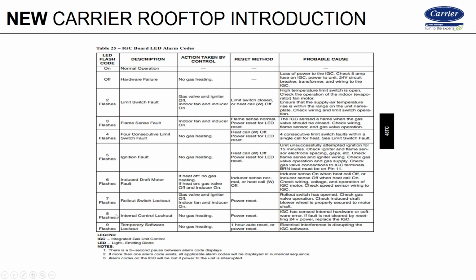So fault code 8, internal control lockout. There's a few things that cause this. Either the IGC board is bad, but before you condemn it, if your rollout circuit or your limit circuit has a ground in it, that can cause a fault code 8. If your gas valve is grounded, it can cause a fault code 8. If you change the gas valve out and you reverse the wiring, your common to your 24 volt wiring, that can cause a fault code 8.